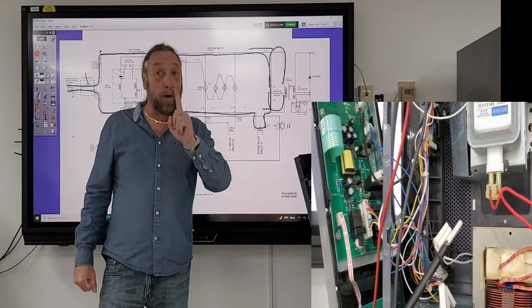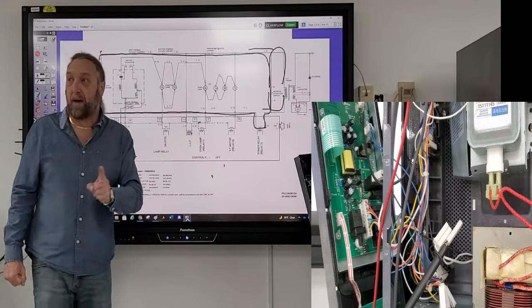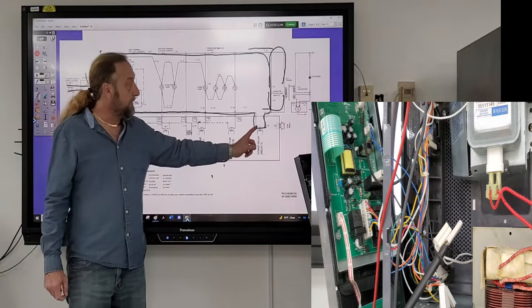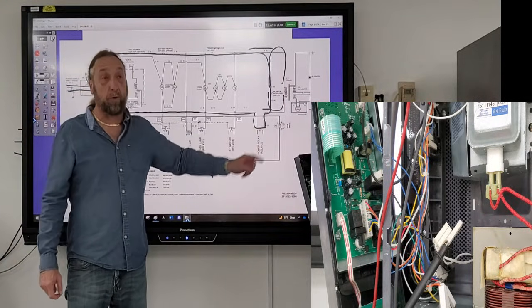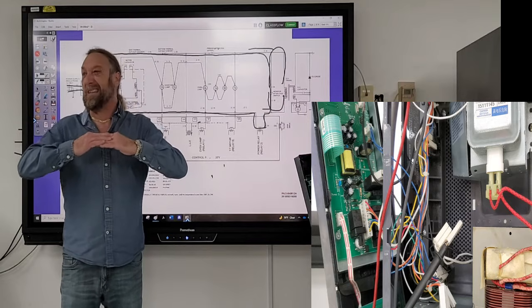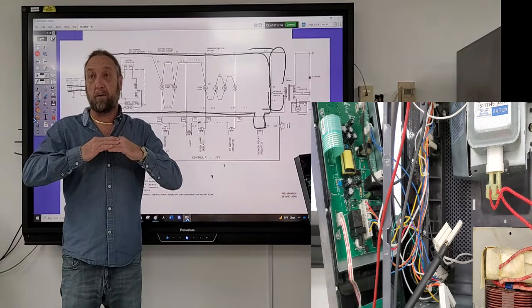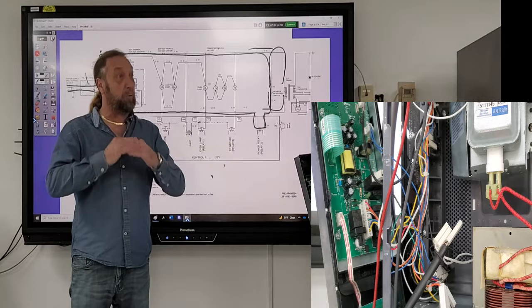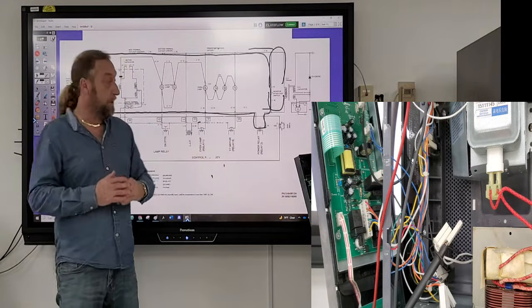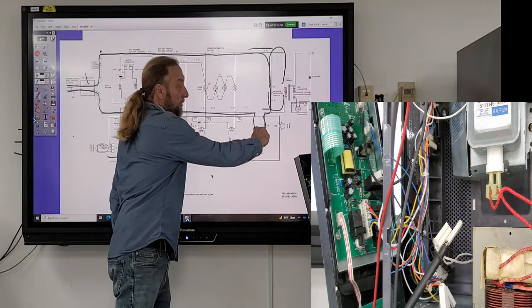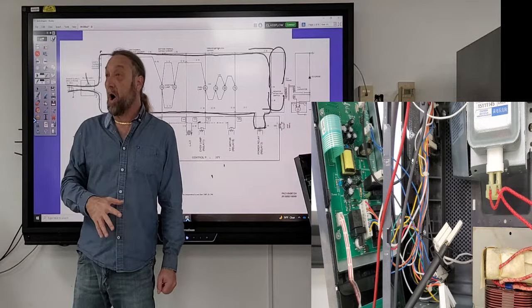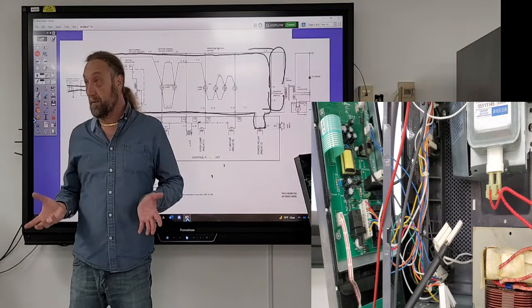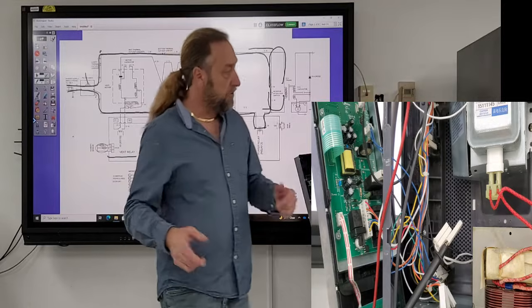Now, one of the things that happens, and you have to check this out, is that sometimes when that short goes through that relay, the contact in the relay stays closed. So if you see that it blows the breaker in someone's home, you want to put a meter right on here and make sure that when it's off, that that relay is open. How do you do that? I'll show you that one last thing here.